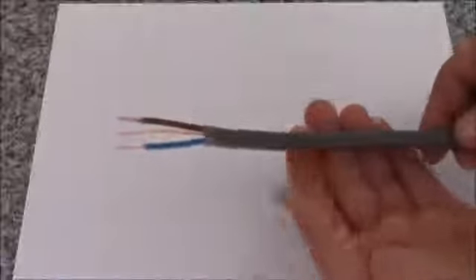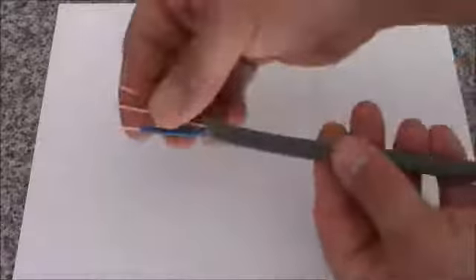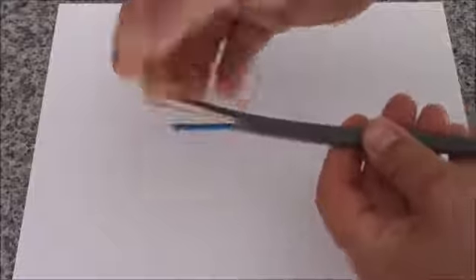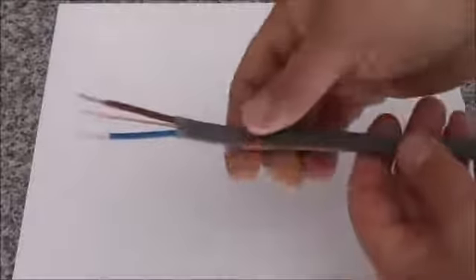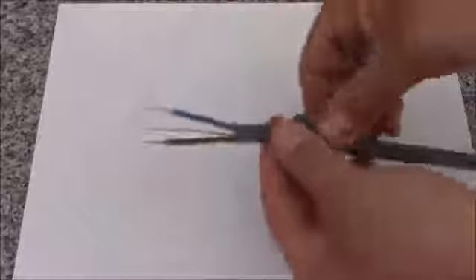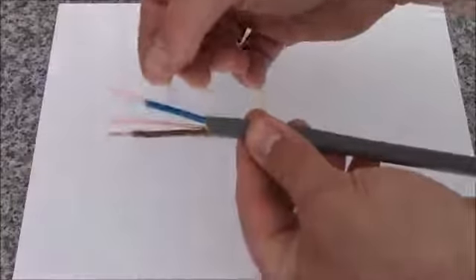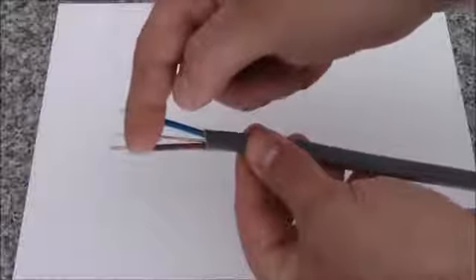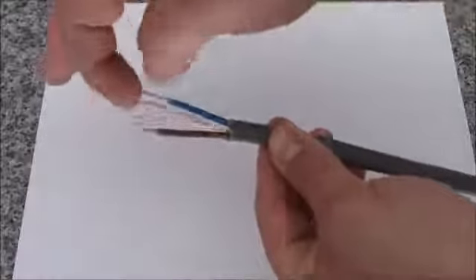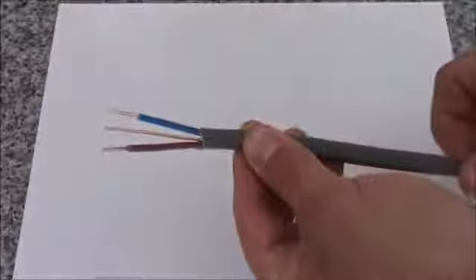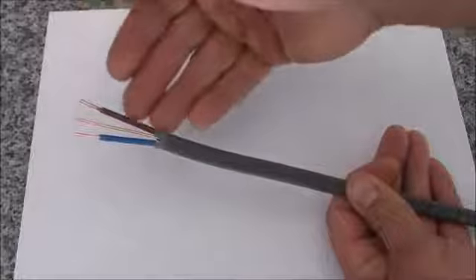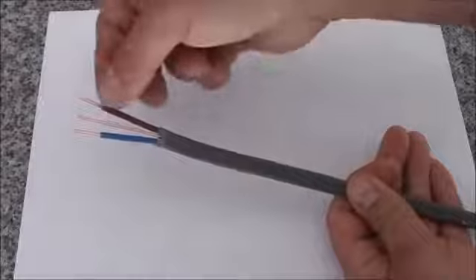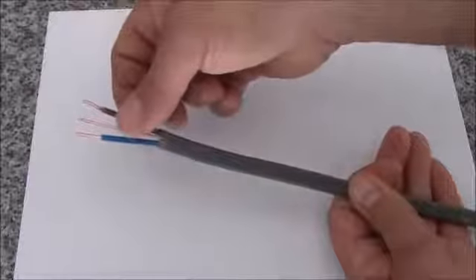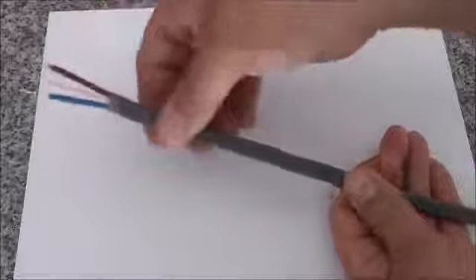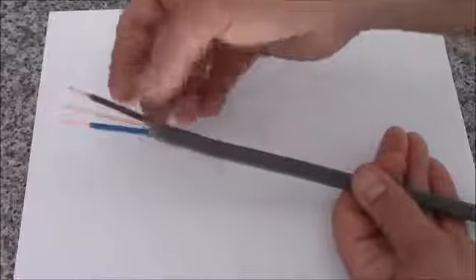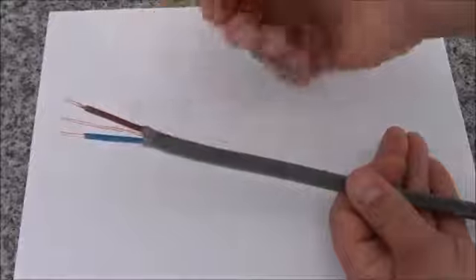So that's the cable, thermoplastic insulated flat cable for domestic installations in the UK. I don't know, in different countries maybe you've got different cables. Basically it's got 3 conductors in it, as you see: neutral, the blue one, line conductor, the brown one, and the bare one is the earthing conductor. All the conductors have some resistance, so there's some energy loss. When current flows through the conductor, it starts warming up, and if you choose too small a cable for the design current, obviously it can overheat.